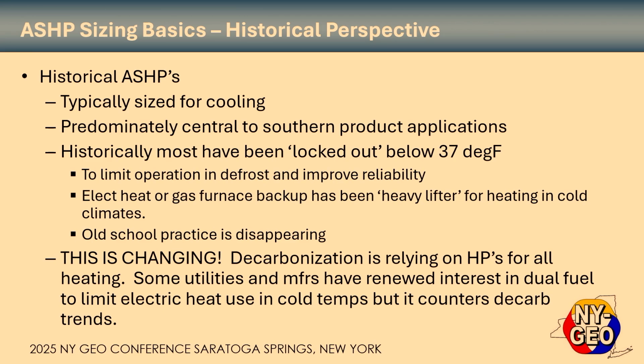Historically, most of those have been locked out below 37 degrees. So when you have a defrost, you've got to switch back and forth to try and defrost a unit at those 37 to 25 degrees. Historically, if I still talk to dealers, there's an awful lot of heat pumps that are locked out at 37 degrees and below. And what that means is you're really running on electric heat when the outdoor temperature is below 37. To limit operation in defrost and improve reliability is really the impetus of that.